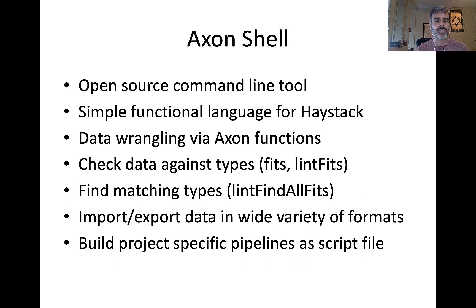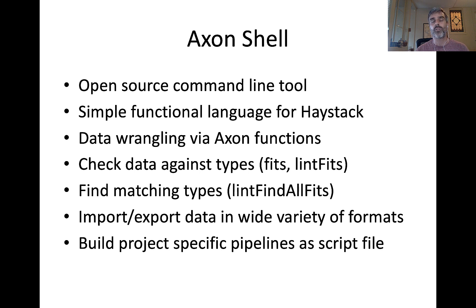We're going to do all our data wrangling as a series of Axon functions. The most important ones are fits and lint fits. Fits takes a piece of data, typically a dictionary, and checks whether it fits a particular type template — returning true or false. If you want to know why it doesn't fit, you use lint fits. Then there's lint find all fits, which lets you go through your database and find all the different types that fit your equipment, spaces, and points. Axon also has a large library for importing and exporting data in a variety of formats: CSV, JSON, zinc, etc., which you can use for your data validation workflows.